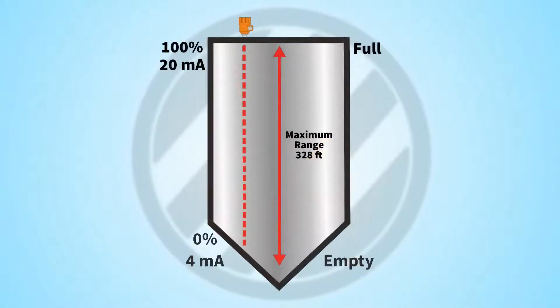Once the radar is positioned, we need to think about the parameters we will input into the program and the milliamp output it will provide. The radar provides a 4 to 20 milliamp loop signal and will usually go up to a digital display or a PLC where the information can be viewed. Setting the range covered by this 4 to 20 milliamp signal is key to an accurate reading — typically 4 milliamps is empty and 20 milliamps is full.